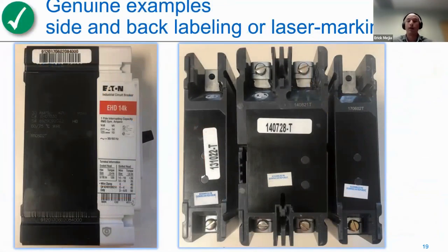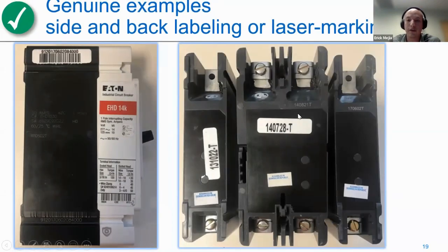So this right here is an example of an authentic EATON breaker. One thing you can notice is there's laser edge printing on the breaker, and that's something you can look at to know it could be authentic. Now, what we're hearing and seeing is that some of these counterfeiters are getting very shifty in their craft, and they're actually doing these imprints on the breaker now. But here, if you look at the date code, it's in the labeling as well, and it shows being assembled in Dominican Republic.